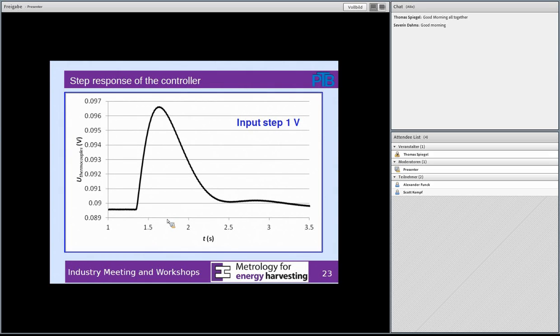Well, if I would ask a different way, you have a 1 volt range device. If you measure 0.1 volt, does that mean that you already need to use an amplifier for accurately measuring the signal? Or if you go to 10 millivolts, you have to use the amplifier, or is the device still okay? I would not use it to less than 5% of its nominal output. Probably only down to 10%.